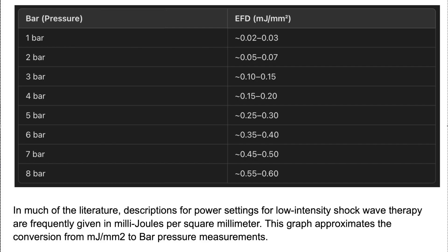Using the International Society for Medical Shockwave Treatment guidelines for the treatment of different body conditions with shockwave therapy, you'll notice that most of their energy recommendations are in something called energy flux density, which is millijoules per millimeter squared — probably the more precise way to measure shockwave therapy energy.